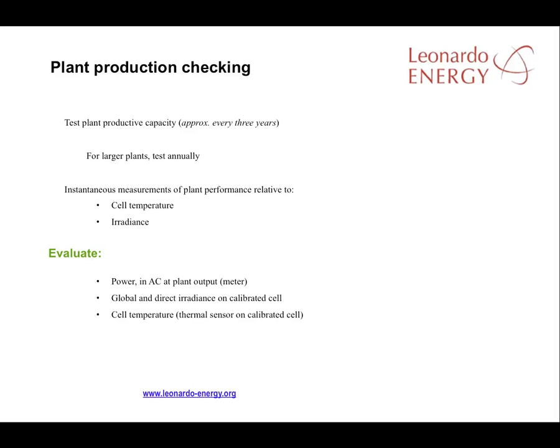You can evaluate the plant's output using the meter and then check performance against the global and direct irradiance, and against the performance of a calibrated cell. It's important to use a calibrated cell of the same technology type as the panels if the measurement is to be meaningful.